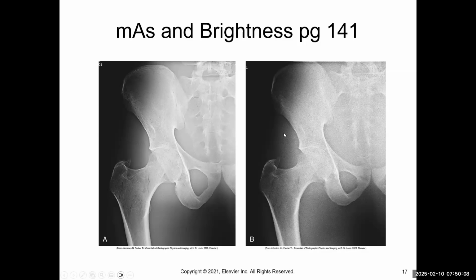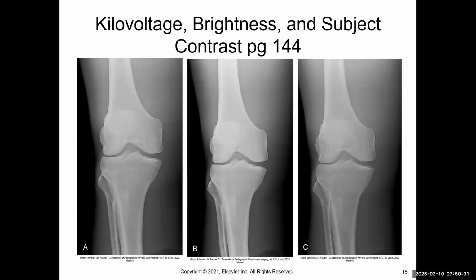There's a lot of noise in there. Y'all see it? And if you look at your books, you can see all of this graininess in this image that we don't see here. This one is so nice. And do you see how that noise obscures some of these lines and things that may be important in the image? So that's why we want to be sure that we are not only checking our EXI numbers, but that we're also checking the image itself for noise.